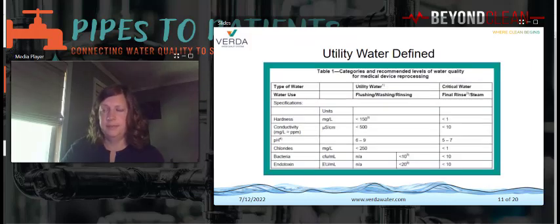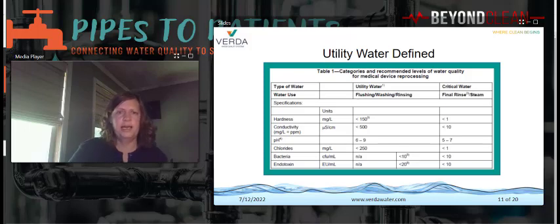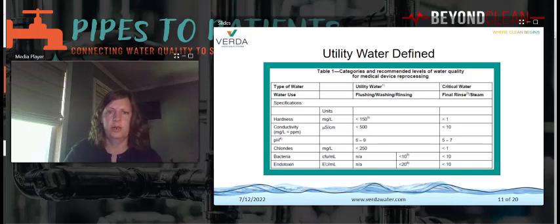So here's utility water defined. This is Table 1 from AAMI TIR 34, and it defines the characteristics and specifications for utility water and critical water. Of all the parameters, the bacterial level is the one most customers are concerned about. Bacterial is important, and it's the one parameter, if not met, that will result in shutdowns. But the other parameters should not be ignored. Water hardness for utility water has to be less than 150 milligrams per liter. Critical water is less than 1. The critical acceptance level for hardness for critical water is so low, sometimes it's below the accuracy of test strips and below the minimum reporting level capability of some water test labs. Also, some municipal supply water can exceed the 150 milligrams per liter for utility water, especially during different seasons as the water source changes.